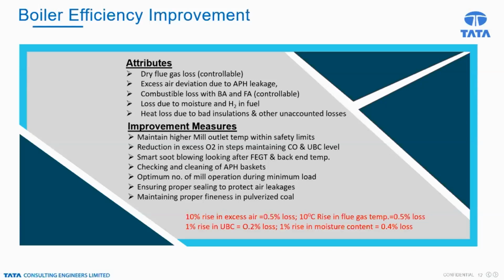And obviously the unburned carbon in the ash will also lower boiler efficiency. Of course, an increase in the moisture content also will increase the loss. So one parameter is boiler efficiency, and we have to operate the boiler at the highest possible efficiency at any point of time, given the variables, because we will not always be having the design goal.